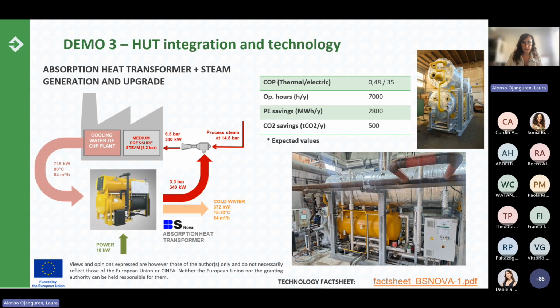And when we talk about the electrical COP, this is much higher because, as I said before, the electricity consumption of the system is very low. The electrical COP would be even higher for only the AHT, but when we combine this with the external system for producing the steam, it's a bit lower, around 35. Okay, and with the estimated operating hours per year of 7,000, we will have primary energy savings of around 2,800 megawatt hours per year and savings of around 500 tons of CO2 per year.